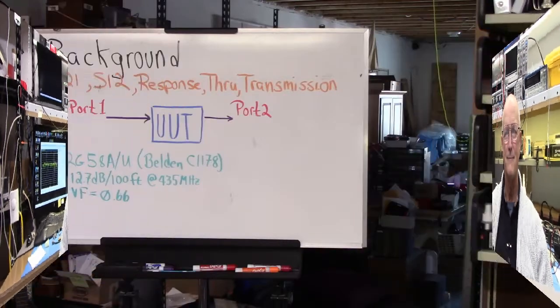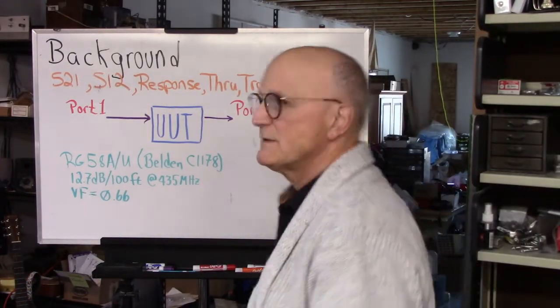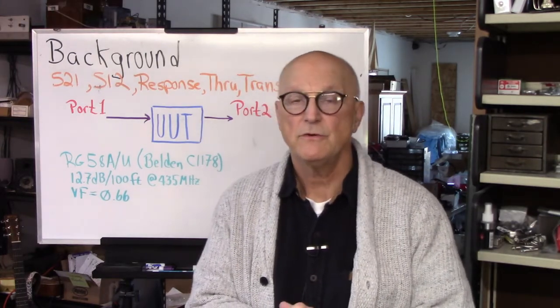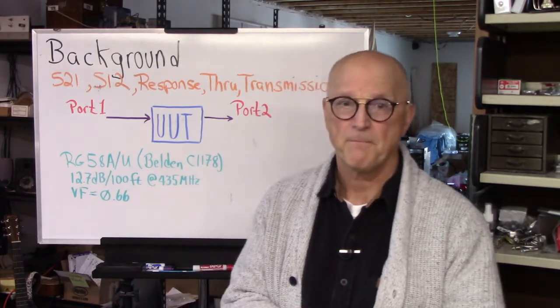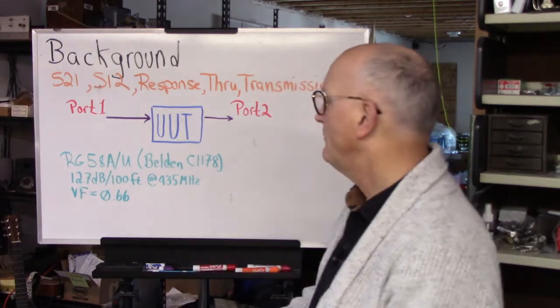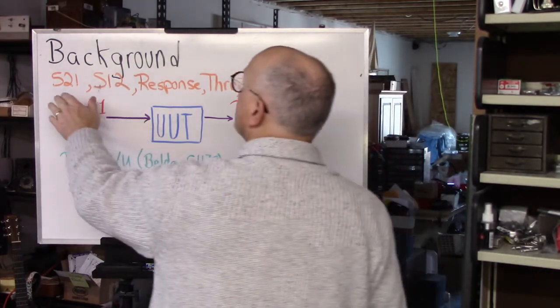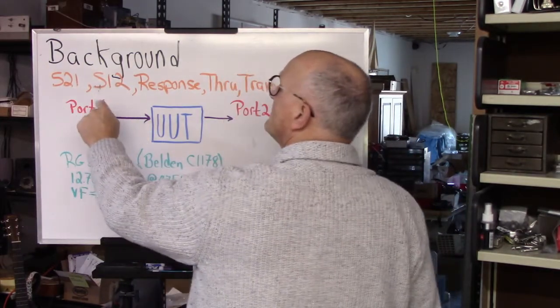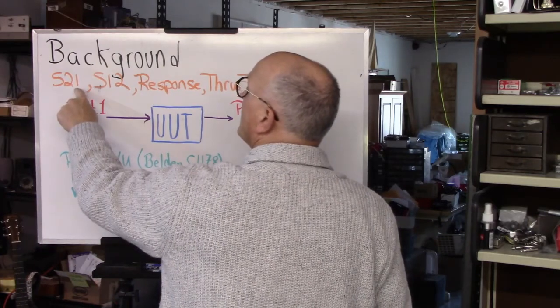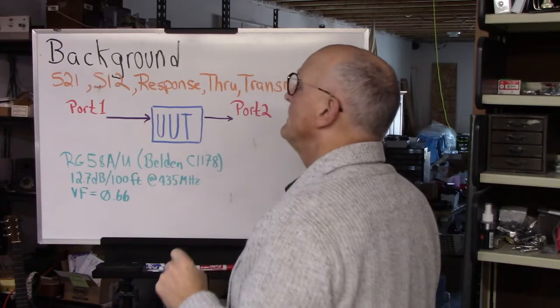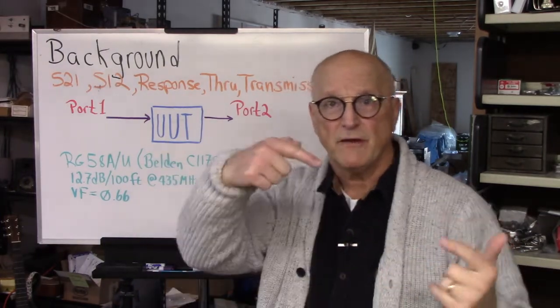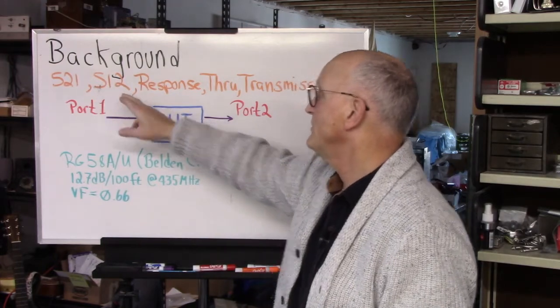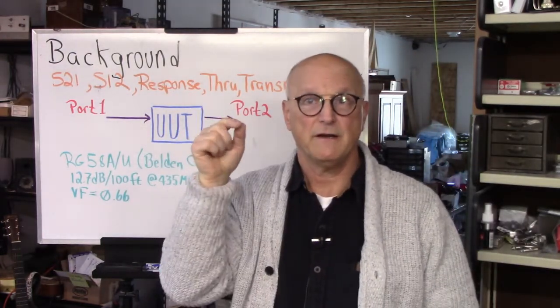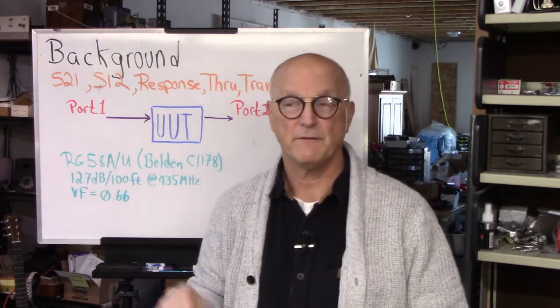So let's go into two-port calibration and measurement, the foundations. So let's talk about some background with regard to two-port VNA calibration and measurement. With some VNAs, the two-port measurements are referred to as S21, which means the signal is starting at port 1 and going to port 2. And the higher end VNAs will let you go the other direction and refer to it as S12, so the signal's originating on its port 2 and going to its port 1.